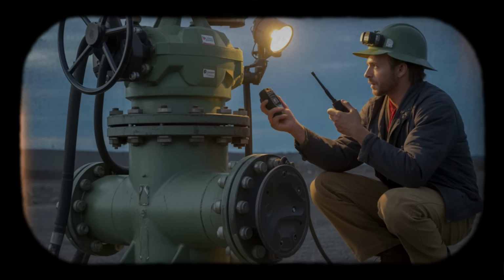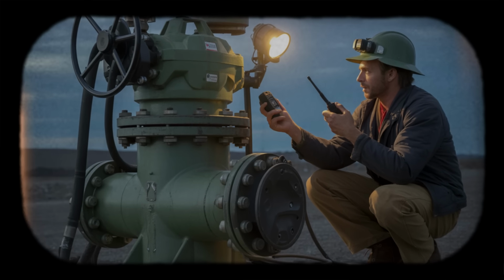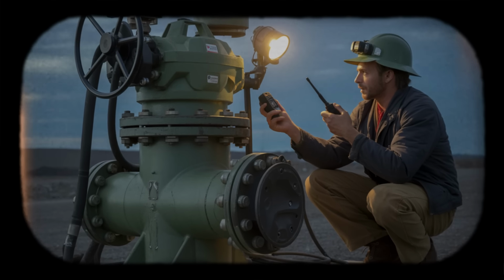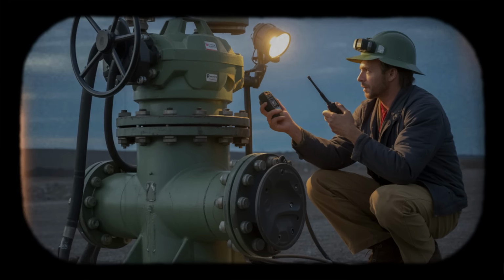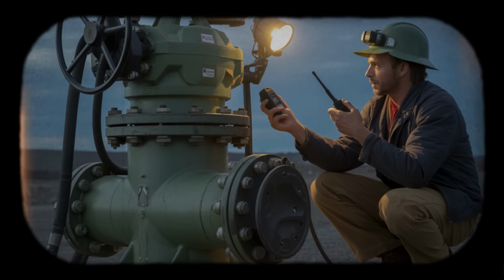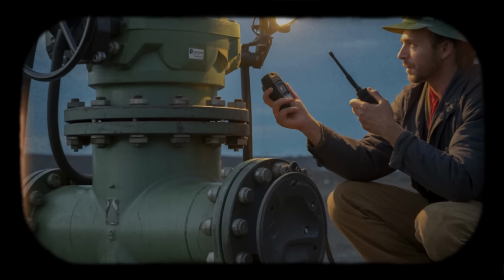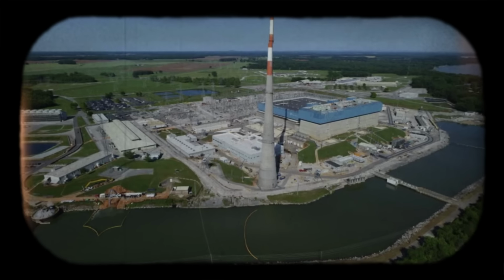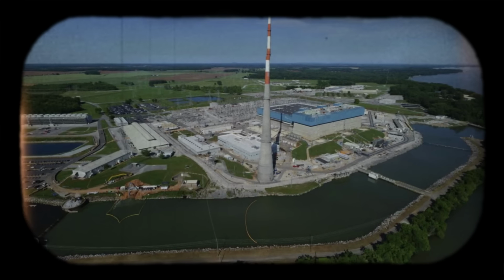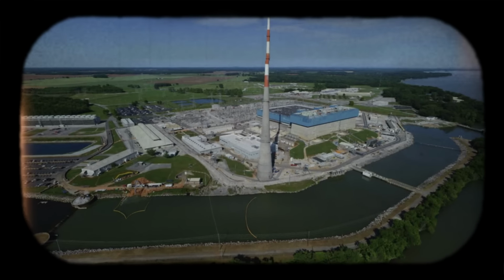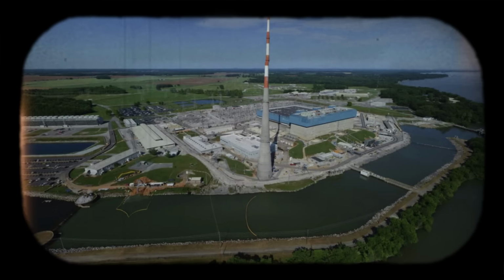The radio becomes the lifeline. Control room operators maintain continuous communication with personnel at RHR pumps, at core spray initiation valves, at torus spray distribution headers, and at suppression pool temperature monitoring points. Each person becomes a human sensor, reporting observations that substitute for failed instrumentation. The human element replaces the electronic network that fire is destroying.